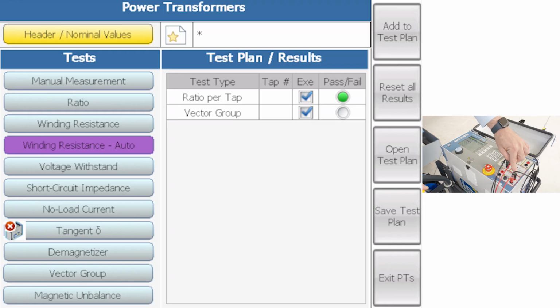And from 6 amp, from the source, we are sending it to the ammeter. Here, we measure this current with a very accurate ammeter because the accuracy is very high, 0.2%. And this wire goes to the secondary side of the transformer, to phase A. And in order to close the circuit from neutral, I close the circuit here. So once again, generating current, going to the ammeter, measuring current, sending the current to the transformer, and returning from the transformer to close the circuit here.